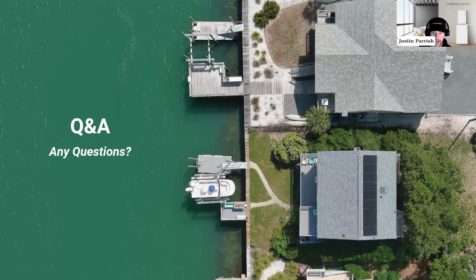An average fridge, add another 3 on there, no problem. Again, AC, as long as you're a 5-ton or less, absolutely. To be honest with you, there's a beta site that has a 3-ton and a 3.5-ton, and I was there. It ran both. So if there was such a thing as a 6.5-ton HVAC, a single aPower 2 can handle it. So really, the second part of your question is the most important.